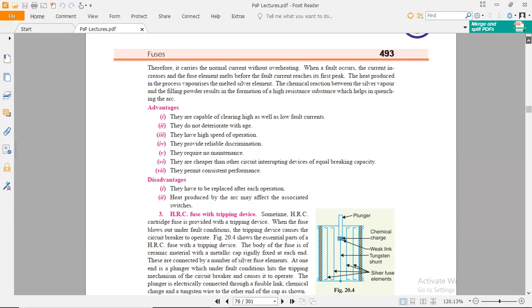When the fault occurs, the current increases and the fuse element melts before the fault current reaches its first peak. The heat produced in the process vaporizes the melted silver element. The silver element is in place between the endpoints. The chemical reaction between the silver vapor and the filling powder results in the formation of a high resistance substance, which helps in quenching the arc. The quenching mechanism is to manage the arc and contain it in the whole fuse housing.